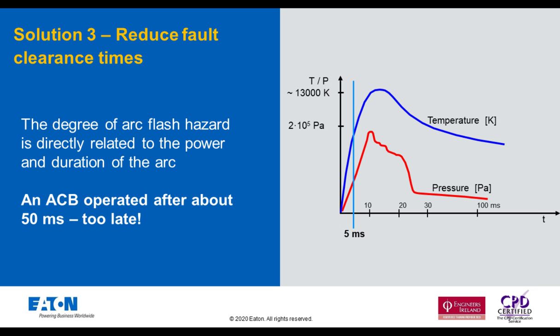If we consider the necessity for personal protection, if you look at the graph on the right-hand side, you can see after 10 milliseconds the pressure reaches the maximum in the vicinity of the arc, and it gets up to a level of around 200 kilopascal. Then after about 15 milliseconds, the temperature of the arc reaches around 13,000 degrees. So you've got two effects that are really happening within about 15 milliseconds.